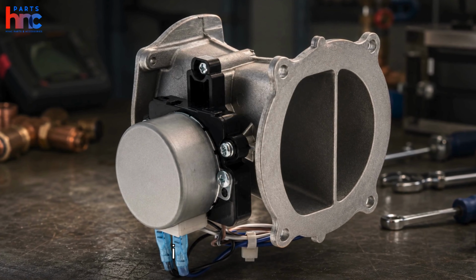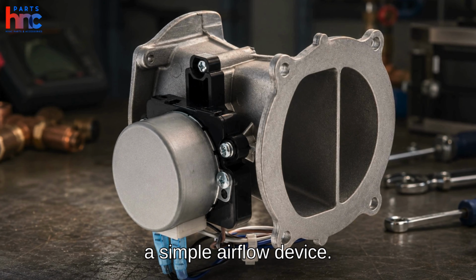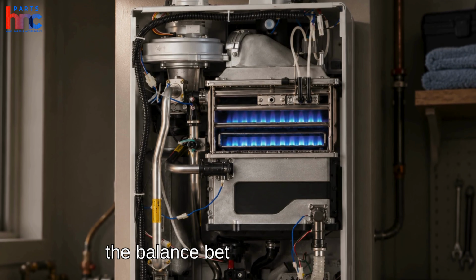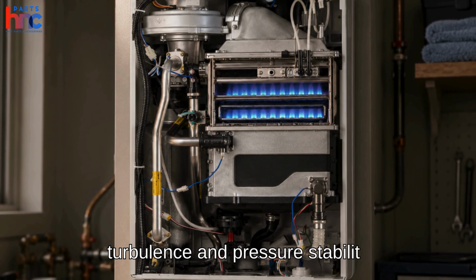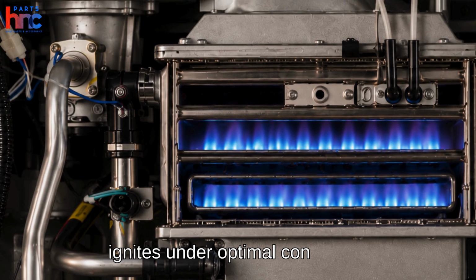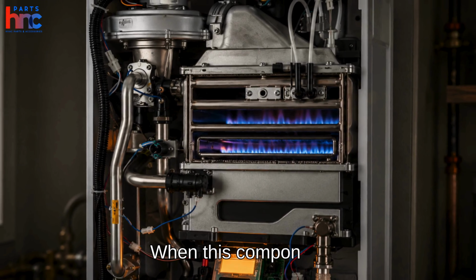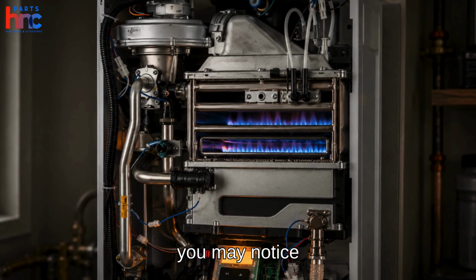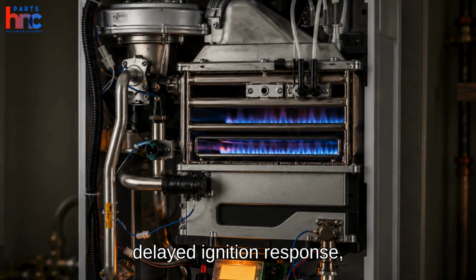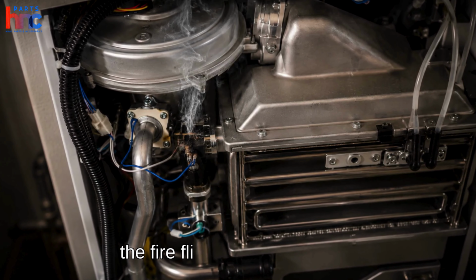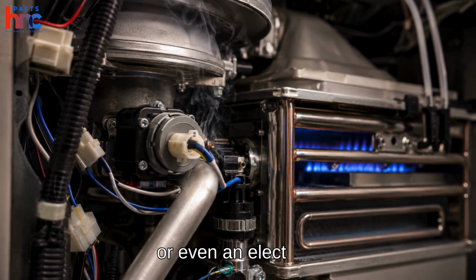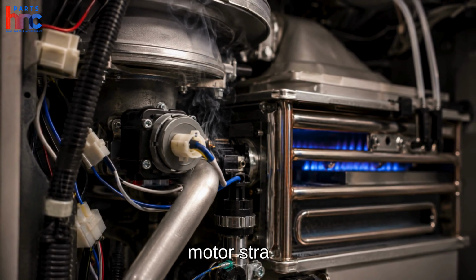The dual Venturi motor is more than just a simple airflow device. It actively regulates the balance between combustion turbulence and pressure stability to ensure the burner ignites under optimal conditions. When this component begins to fail, you may notice common signs like delayed ignition response, flame instability where the fire flickers inconsistently, or even an electrical odor suggesting internal motor strain.